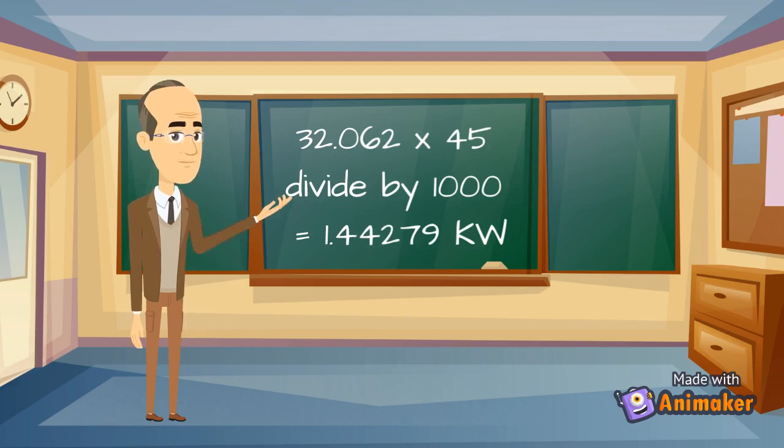Our room size of 32.062 meters cubed is multiplied by the number of watts maximum allowed which is 45 for a space heater in a room. The answer at this point tells us how many watts the appliance maximum rated input can be for that room.